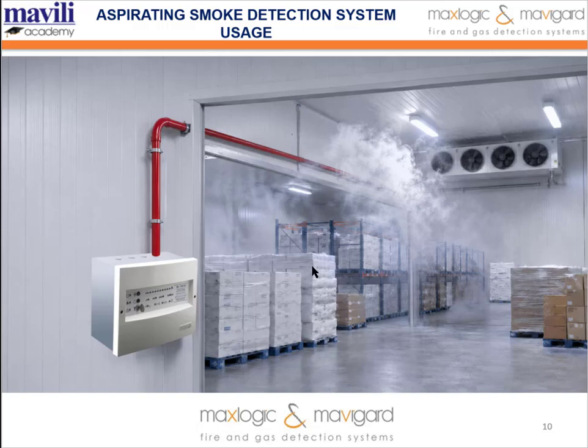So as you know, the other important point is cold storage facilities. So the aspirating smoke detection is preferred for providing early detection in low temperature and challenging environmental conditions. However, air taken from the cold environment can create problems due to condensation, icing, or humidity as it is transported to the aspirating smoke detector device. Therefore, a heating unit used in the sampling line or at the device inlet helps the system operate more stably by ensuring that the taken air reaches the device under appropriate conditions.